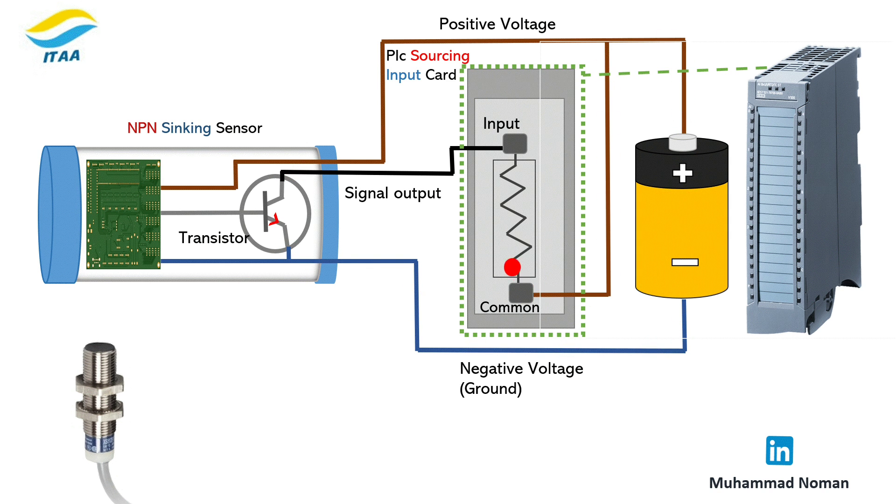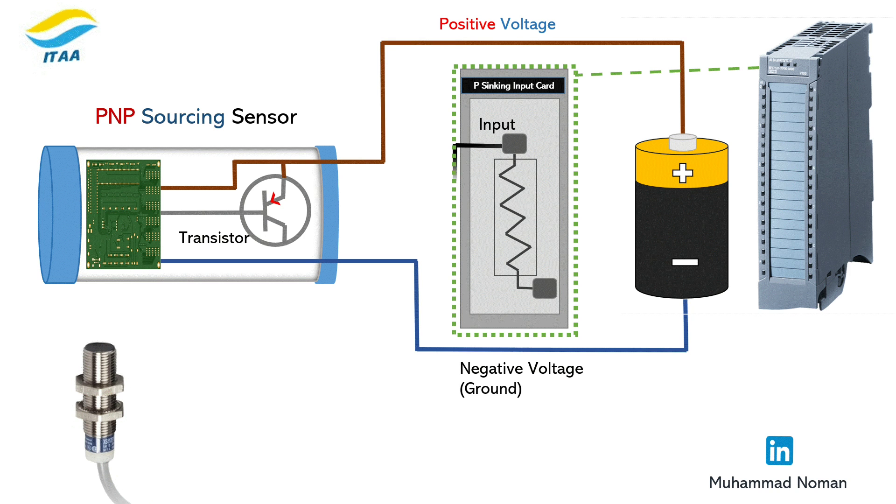For PNP: brown to plus 24, blue to zero, black to PLC input, and COM must go to zero volts (ground).